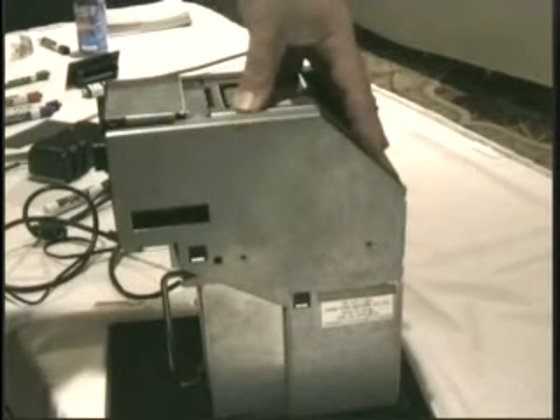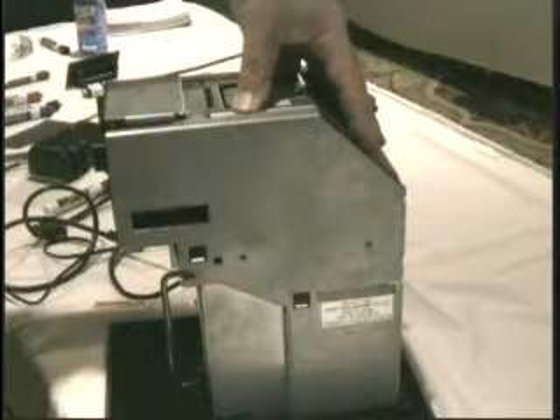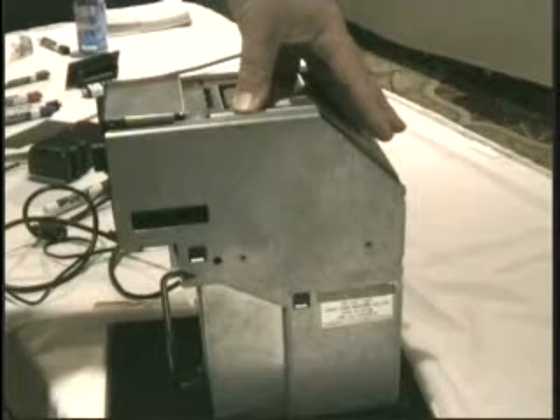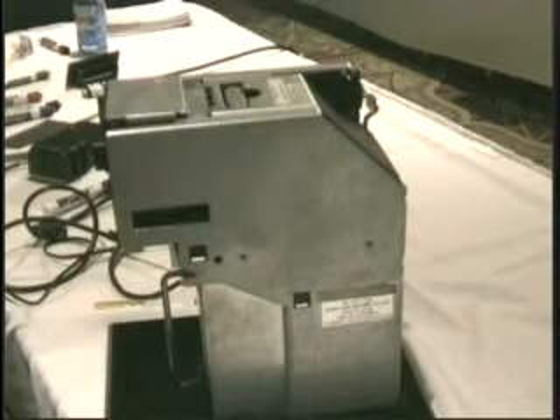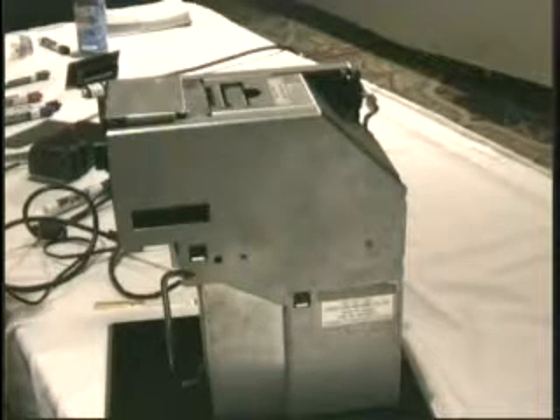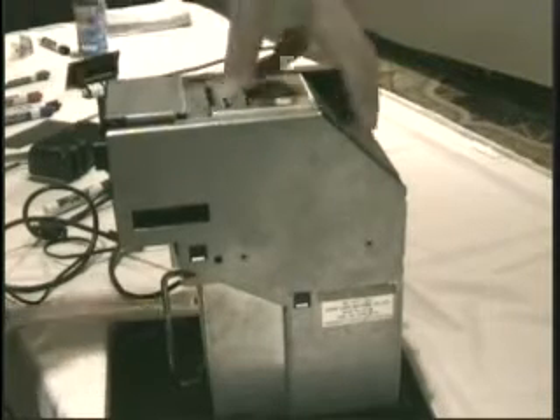We're going to run out of dip switches if we try to check all the sensors individually. We've got 5 optical sensors in the head and 8 optical sensors in the transport -- let me count, 1, 2, 3, 4, 5, 6, 7 -- 7 optical sensors in the transport, had to think for a minute on that one. We'd run out of dip switches if we tried to assign one to each, so instead we separate the head sensors and transport sensors into their own test groups.